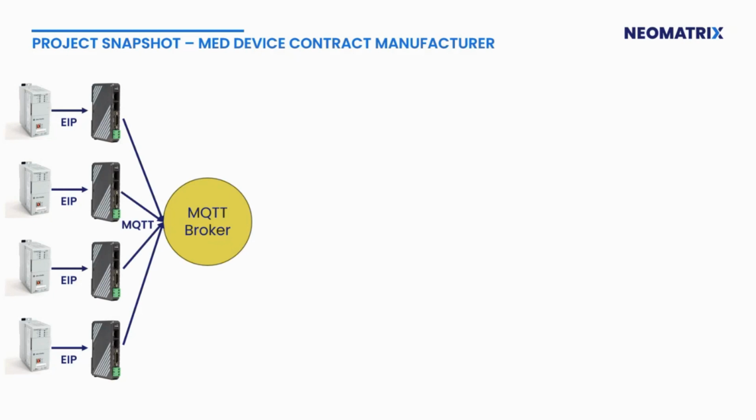And then what we can do is that device supports talking to up to 300 different PLCs, but it also supports publishing to an MQTT broker, right? So we took the data from all of these processors and published it to a unique space in the MQTT broker, right? And essentially for a cost of $500 per line, we didn't have to reverse engineer or change anything or invalidate any warranties that are out there. And we have all our data in a broker now, right?